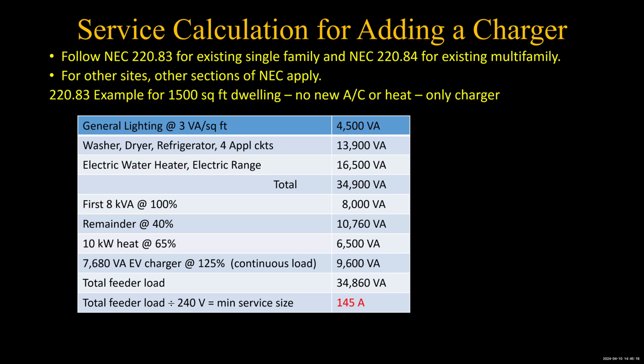We have a washer, a dryer, a refrigerator, and 4 appliance circuits in this place. And each of those with their NEC rated capacity, the total of them is 13,900. Why didn't I list them separately? It would have gone off the bottom of the screen and you wouldn't have been able to see it anyway. Then there's a water heater and a range, another 16,500. So we got a total of 34,900 volt amperes.